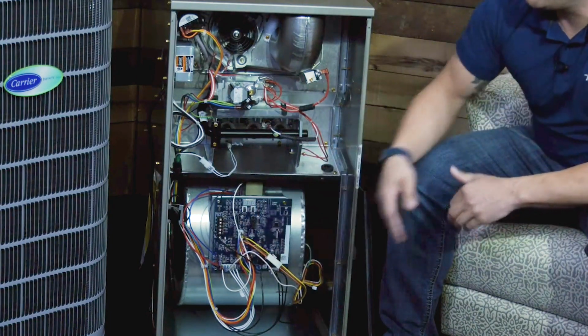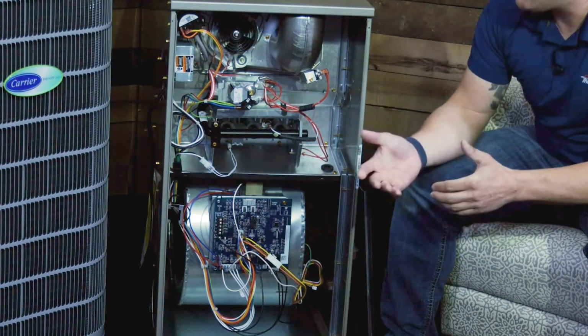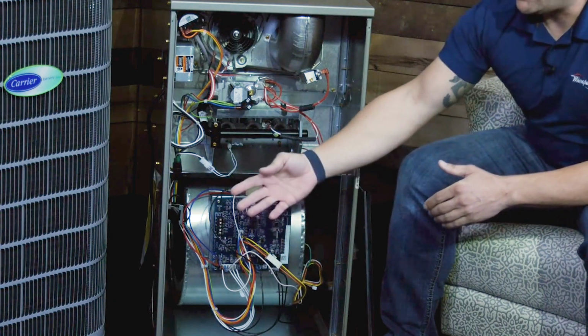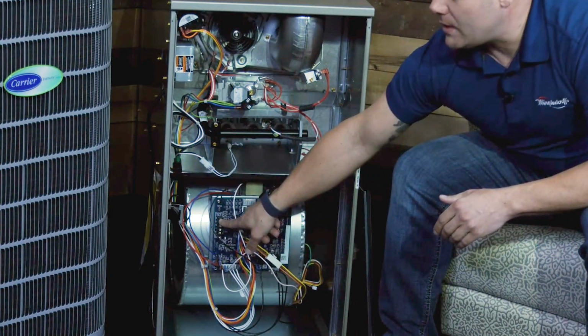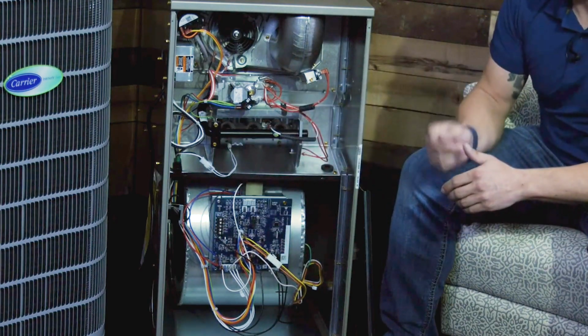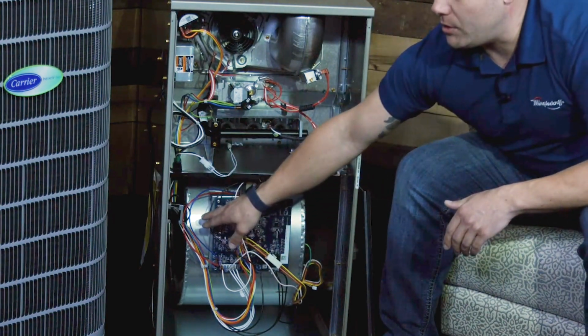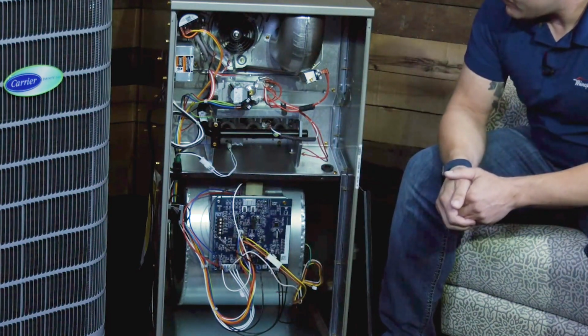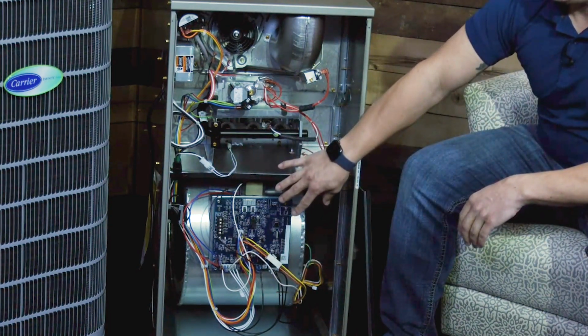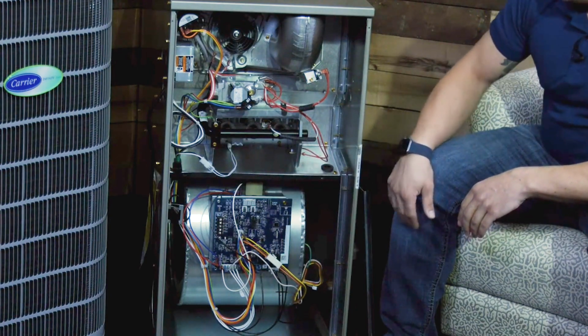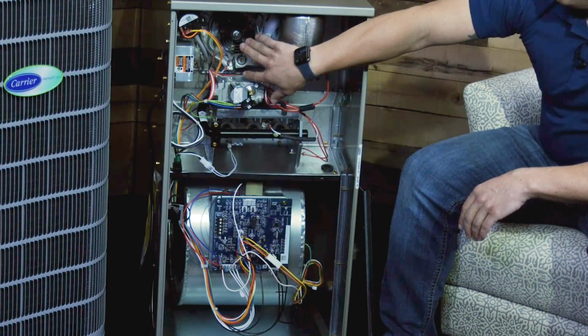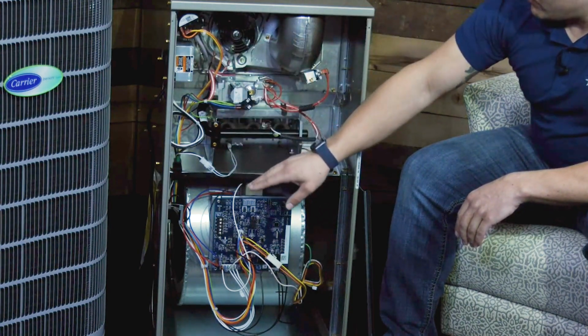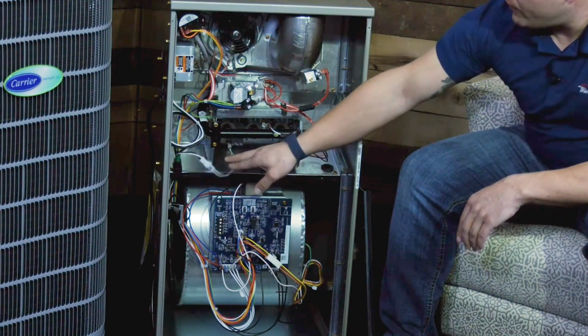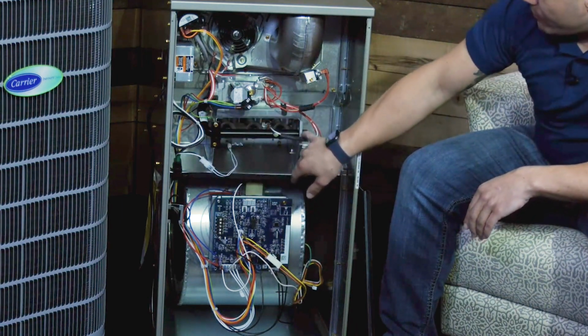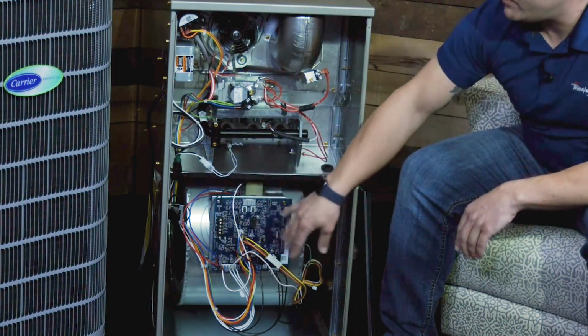And so first would be the 24-volt call to the board from your thermostat. And then sometimes what we do is we can eliminate the thermostat and we'll put a jumper wire between R and W. And that just sends that 24 volts. And then that will just send that call to the board. We know we're getting 24 volts. And then step 1 would be draft-induced motor, and then 2, pressure switch. 3 is igniter. 4 would be gas. 5 is flame proving. And then 6 would be finally the blower motor.